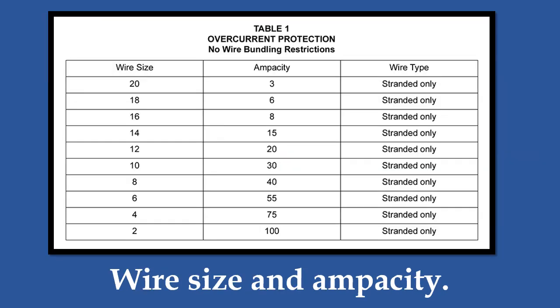Both the individual fuse holders and the panel boards must match the fuse or breaker rating to the low voltage conductors or wires being protected. Also, note that all current carrying conductors in an RV low voltage system must be stranded wire. The most commonly used wire in RVs are the 14 gauge and 12 gauge wires or conductors. Again, stranded wire is required for all current carrying circuits on the low voltage systems. Table 1 shown here details the size wire and its associated maximum overcurrent protection. The small 14 gauge wire requires overcurrent protection at a maximum of 15 amps. The 12 gauge wire requires overcurrent protection with a maximum of 20 amps.